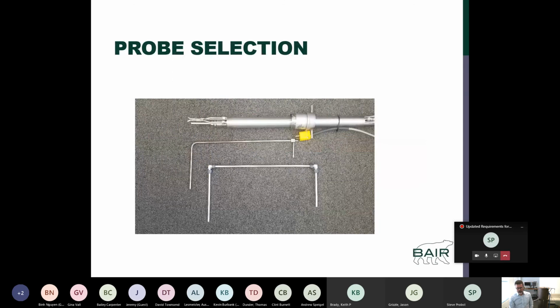So getting to probe selection, in the pictures here, the top probe is what's referred to as a Method 2 probe assembly. There are three components here. You've got an S-type pitot, a sampling probe, and a temperature probe. I'll show one of these to you in just a minute. The middle probe is a standard pitot, and the bottom probe is a manufactured tubing. We can put these together in the field to meet the criteria if we don't have probes or test ports to get our probes into.